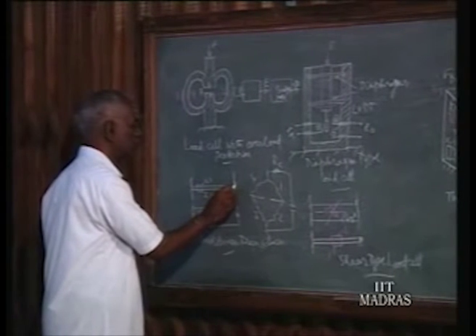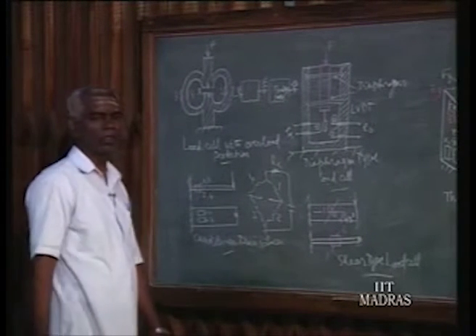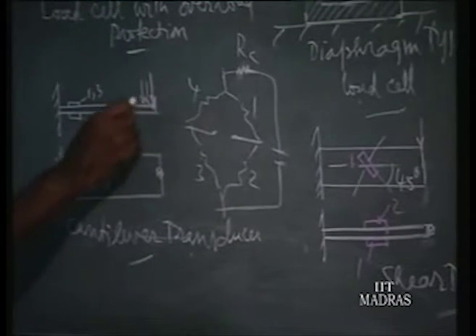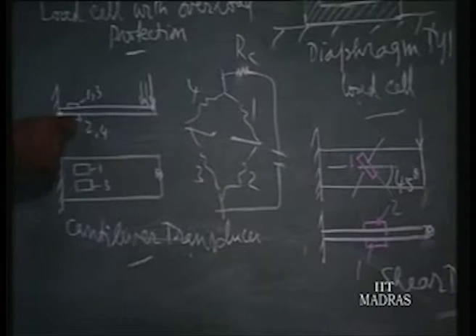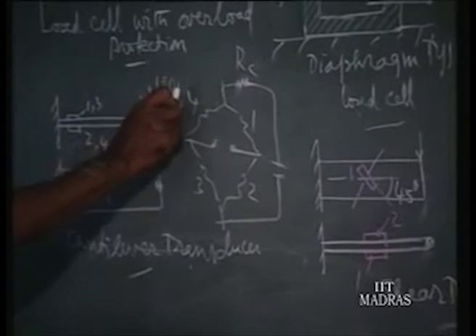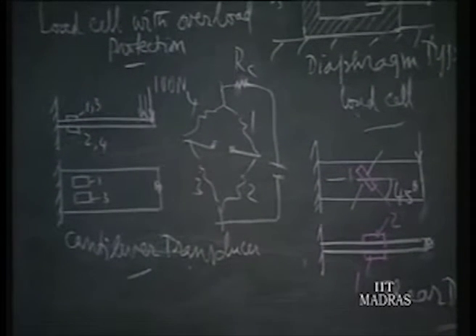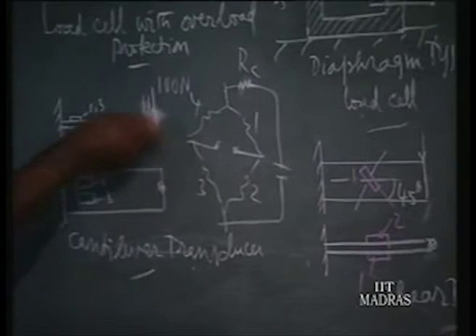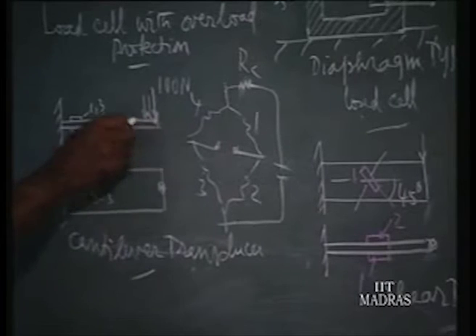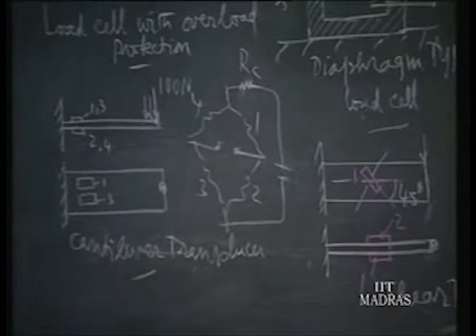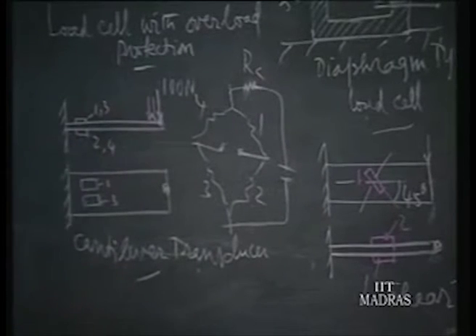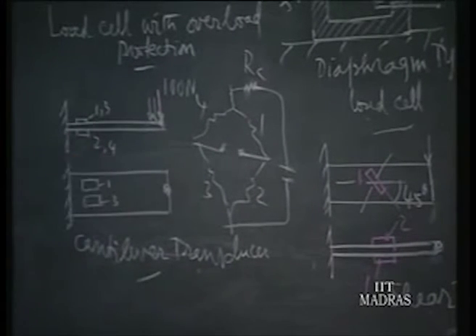The one problem in the cantilever type of transducer is, suppose this is the load button, the place where you are supposed to apply the load or force. If it is changed a little bit, then for the same force you will find a little less strain here in this cantilever. Then the instrument will show a smaller reading. The force may be 100 Newton, but the instrument will show only about 90 Newton. It is because the load is shifted from its original place due to some error. So the instrumentation is very sensitive to the proper placing of the load on the load cell.